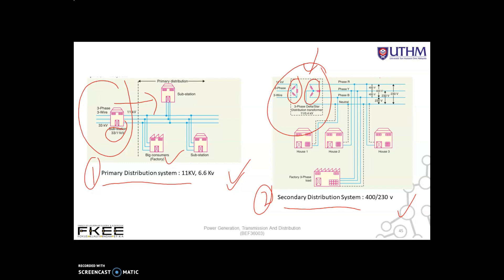From 11 kV to 400 volts, the voltage between any two phases is 400 volts — this is the line voltage. The voltage between any phase and neutral, which we call the phase voltage, V-phase, is 230 volts. The single-phase domestic loads are connected between any one phase and the neutral, using V-phase of 230 volts which is single-phase.